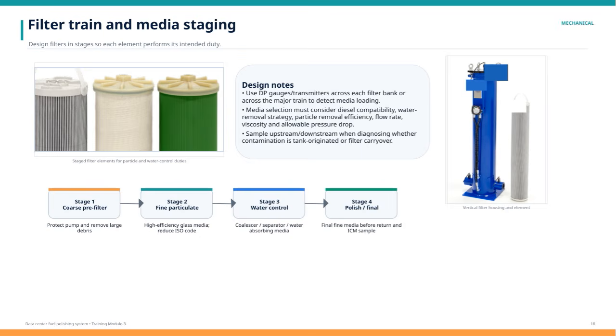A few design notes are important to consider. Differential pressure gauges or transmitters should be placed across each filter bank or the main train to monitor media loading effectively. When selecting filter media, factors like diesel compatibility, water removal strategy, particle removal efficiency, flow rate, viscosity, and allowable pressure drop must be balanced carefully. Additionally, when troubleshooting contamination, sampling both upstream and downstream of the filters helps determine if the issue originates from the tank or is due to filter bypass or carryover. This stage design approach ensures comprehensive fuel filtration and system protection.